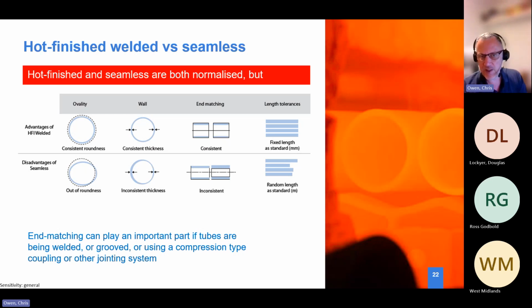And when we talk a bit later about corrosion issues and installation issues, it's worth noting that if you have seamless tube which has different end matchings, when they're welded together or joined together, there could actually be some steps internally, and that could act as an initiation point for corrosion or a place where debris can collect.